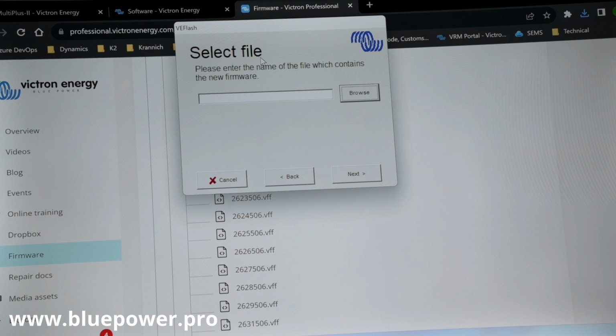I don't put the input on, I just configure my battery, then I put the inverter on, then configure the touch to all its right settings, enable two-way communication, go online on VRM while I'm on site, and then load the firmware and start my setup. You can do it that way, but if you don't have an MK3, you're going to have to. It's easier and quicker just to do it with an MK3, plug it into the unit itself, and do all the settings. It's exactly the same function as doing the gateway.